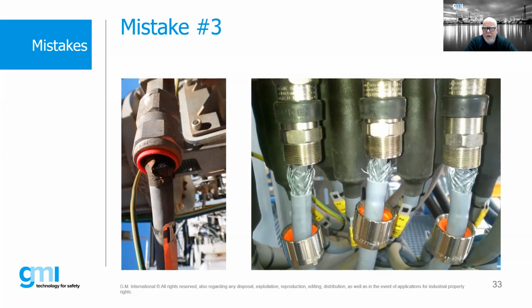But what we're seeing here on the first, the slides over on the left-hand side is obviously damage to the cable. And then on the right-hand side, when we start pulling off the shrouds and looking at the cable glands, we see that the armor has not been landed on the inside of the ring. So it's common practice for inspectors when we do inspections on cable glands, we're not necessarily going to open up every single cable gland in a facility or on a skid, but we're going to do a sample representation. Now, I promise you the picture on the right-hand side, those three glands all were improperly installed. If I was doing that inspection, I would assume that all of the glands that are installed underneath those shrouds are probably not properly installed. And I would say, hey, we need to redo those.